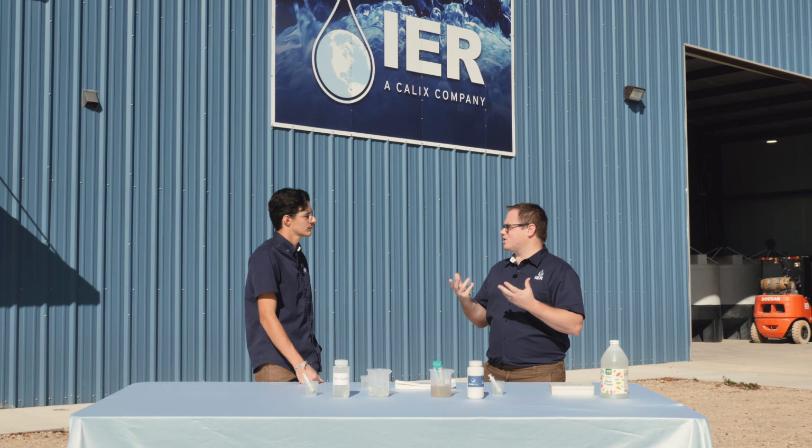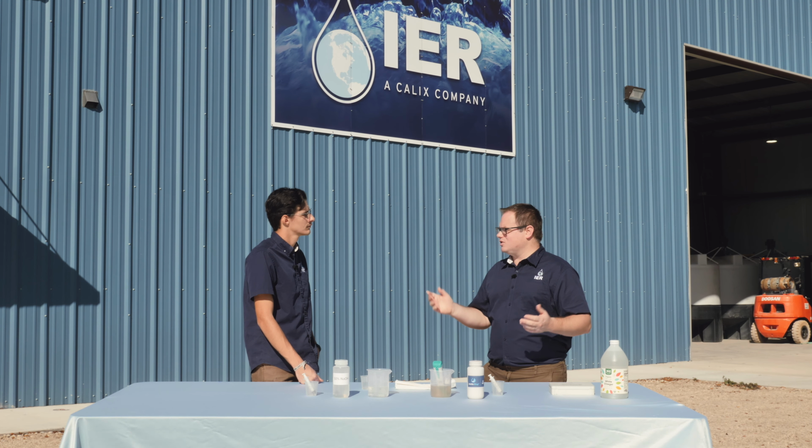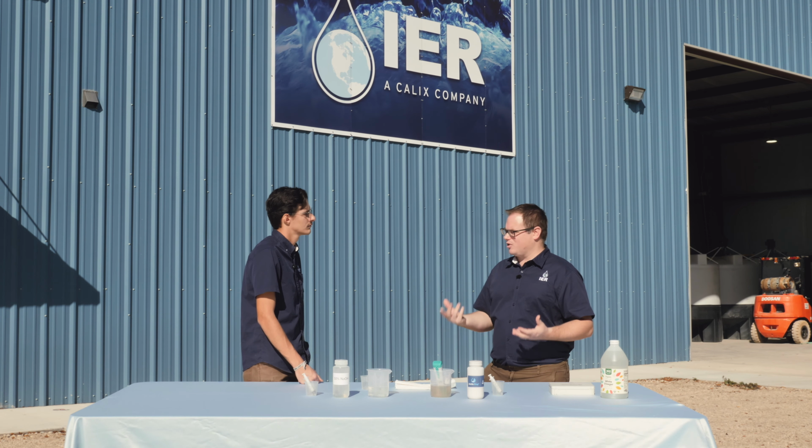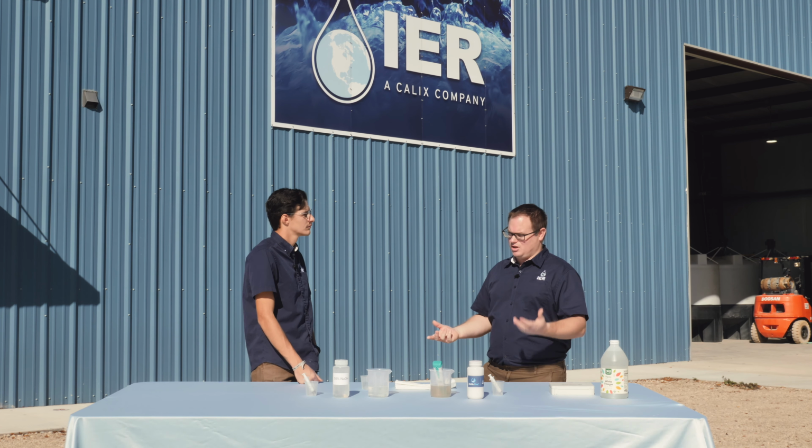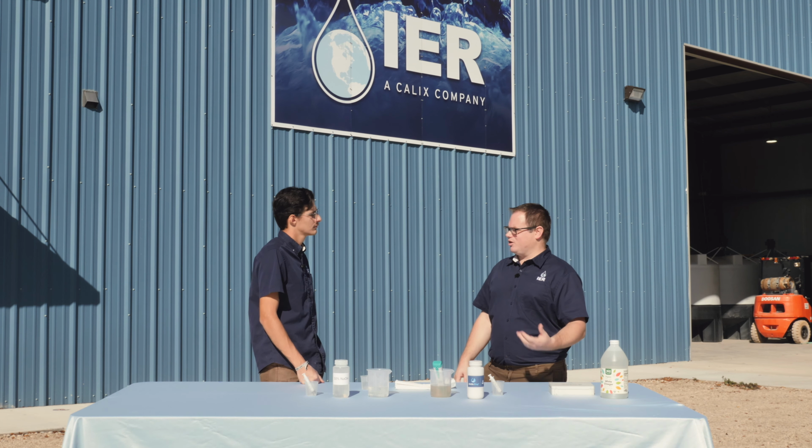So where magnesium hydroxide, once you get up to about a pH 6.5, 7, what's not needed stays in your water, ends up in your activated sludge, and it's just there ready to be available whenever your bugs excrete some acid. They can react with it, bring your pH up, and you now have a buffering capacity built into your system while you're controlling your pH.